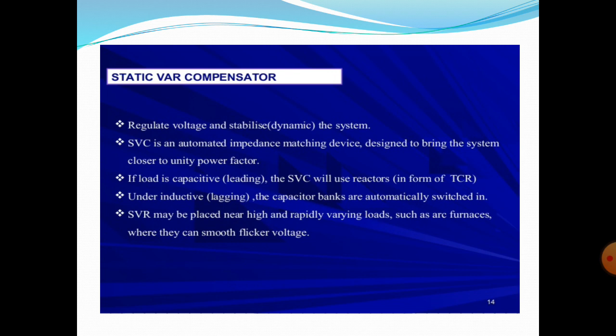If the load is capacitive, the SVC will use reactors in the form of TCR. But under the inductive load, that means the lagging, the capacitor banks are automatically switched in. The capacitor banks improve the power factor. The SVC is based on a thyristor without gate turn off capability, but it includes separate equipment for leading and lagging VAR.